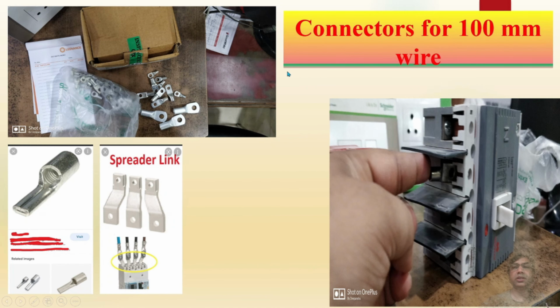Here you can see this 100 mm wire. To connect it to this MCB, you need a specific size of lug like this one I bought. I struggled a lot for this, with a lot of communication with Havells and local electricians - some willing, some not. After traveling to the market around 4 times, I finally got all these kinds of lugs, and then understood that a Spreader Link like this can also be installed to connect a 100 mm wire to this kind of panel.